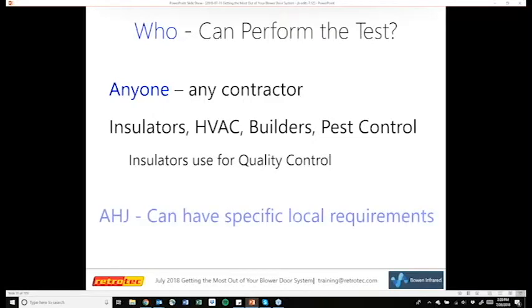So who can do a blower door test? Well, in a lot of codes, if you're just doing it for code, you need to see what the local code says. But typically it's just about anybody. The GC can do it, the insulator can do it, HVAC contractors are usually allowed to test it. They're even allowed to do duct tests on their own work in most cases. The builder can do it, pest control. Sometimes the permit owner can do it, or the homeowner can do it. Really, whoever the building official gives authority to.